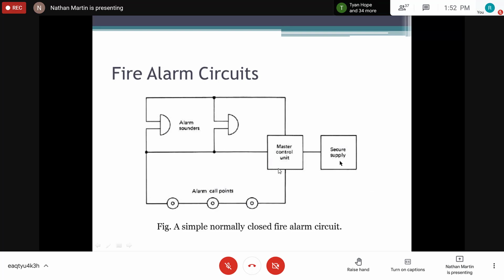So, which is this one now. In the normally closed, realize that if you were to break the circuit at any part here, the alarm will sound and it will go off. However, if you were able to isolate or bridge out one of these devices, then the alarm will not activate, right? So it's a tricky condition when we're talking about burglar alarms and so forth. But this is a simple circuit and they are more complex than this. This is just showing you the different types of sensing arrangement, right?